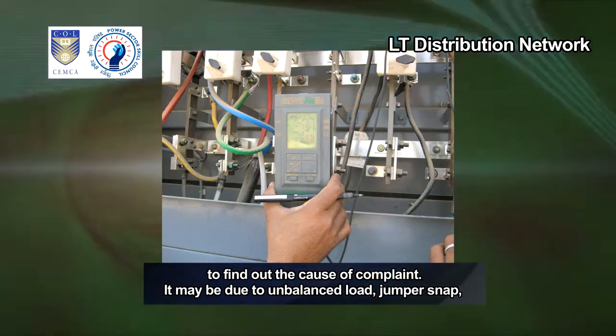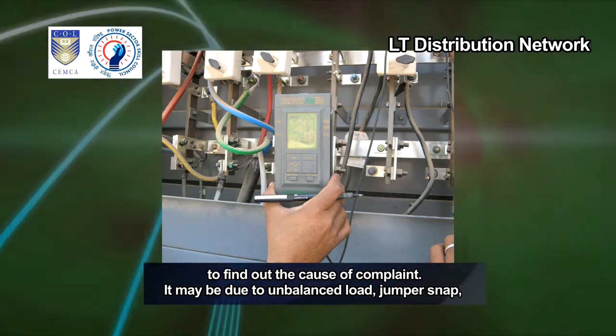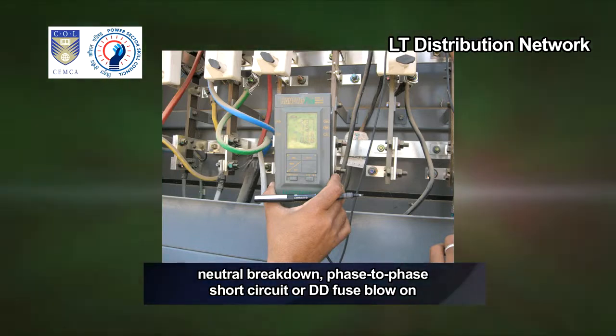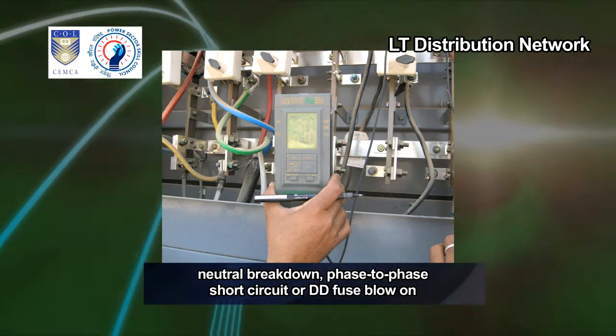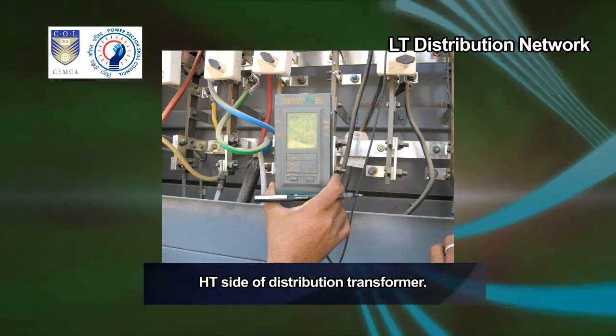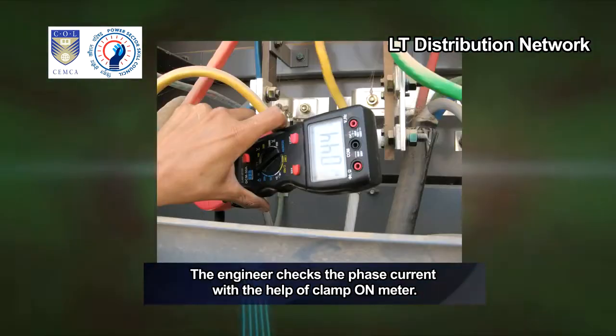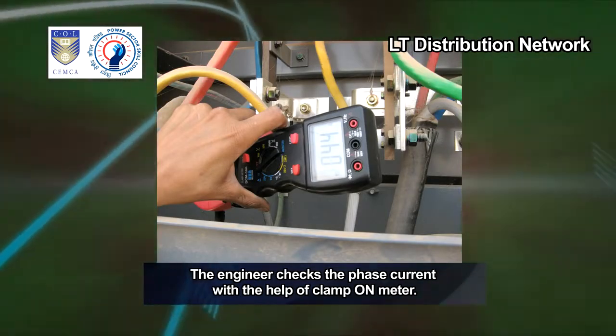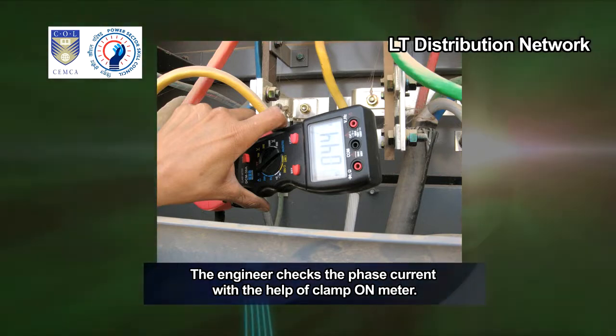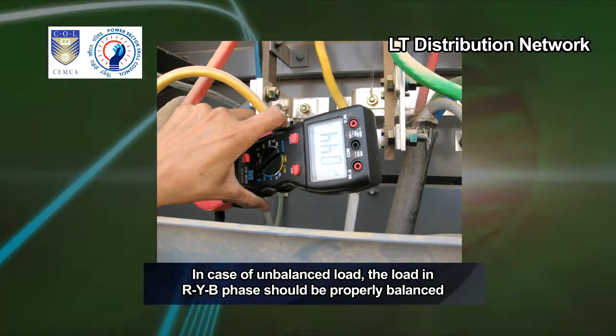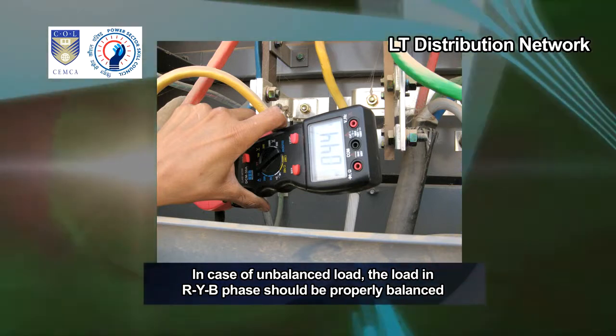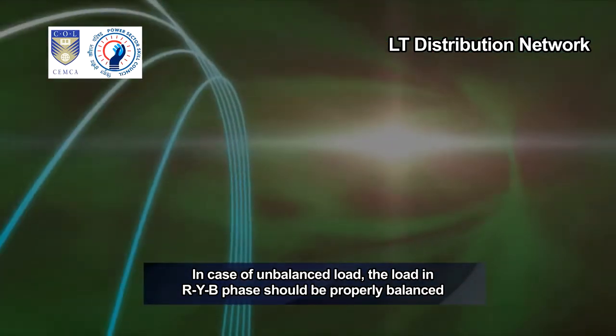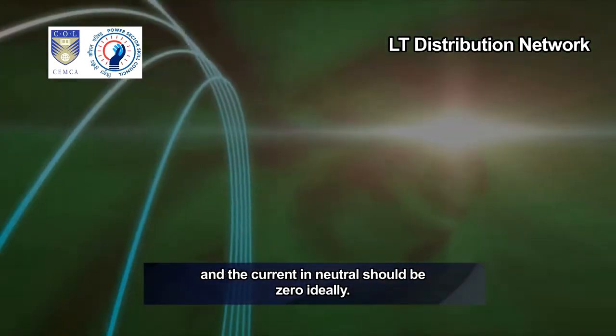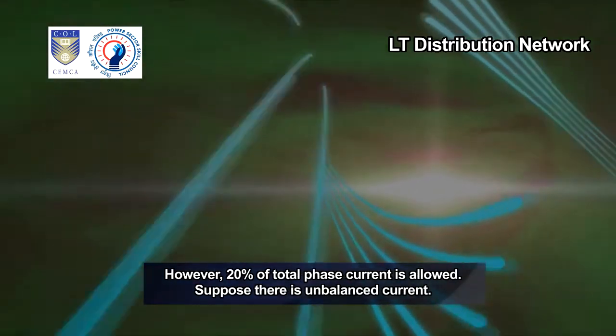It may be due to unbalanced load, jumper snap, neutral breakdown, phase-to-phase short circuit or DD fuse blow on HT side of distribution transformer. The engineer checks the phase current with the help of clamp-on meter. In case of unbalanced load, the load in RYB phase should be properly balanced and the current in neutral should be zero ideally. However, 20% of total phase current is allowed.